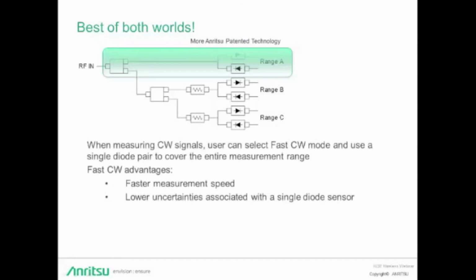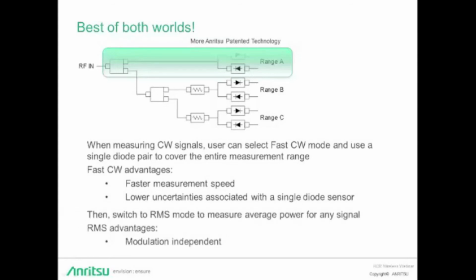In the universal sensors, there is a fast CW mode where one diode pair is used for CW measurements. In addition, with a simple software command, an engineer can switch to RMS mode, where three paths provide a wide range of average power measurement. So, moreover, because it's an RMS sensor, the average power can be determined regardless of modulation type.